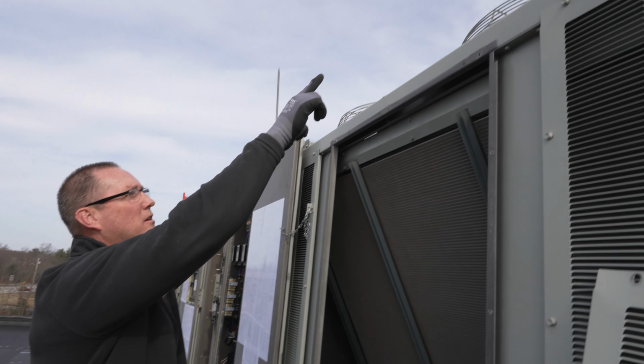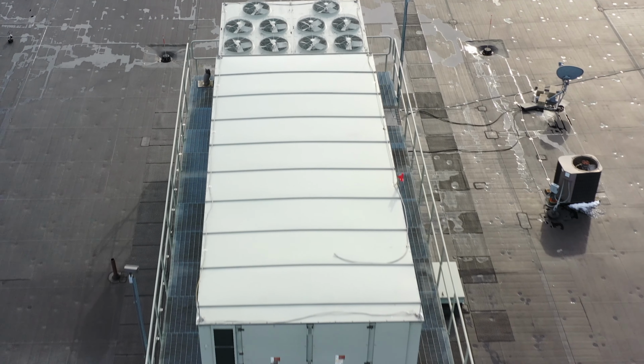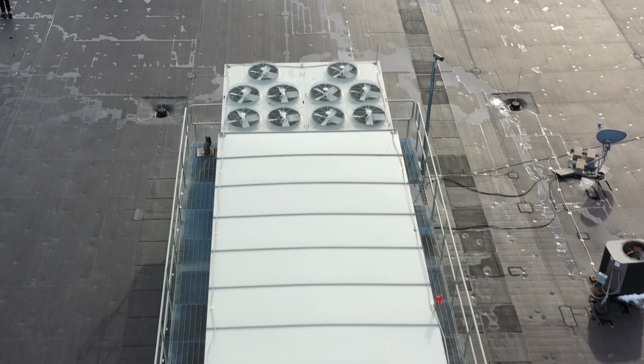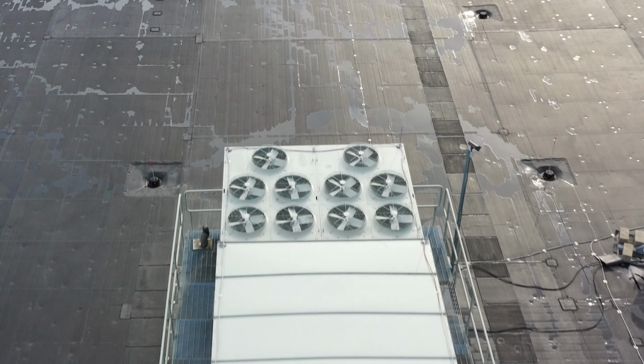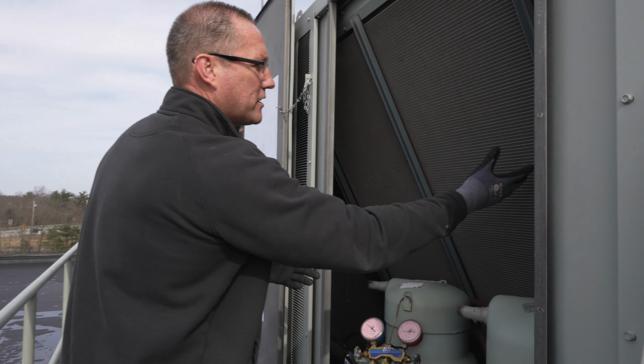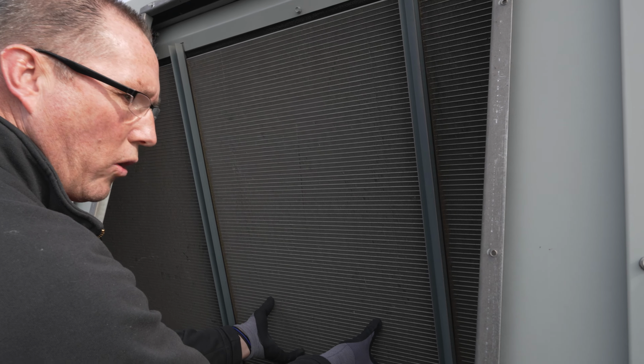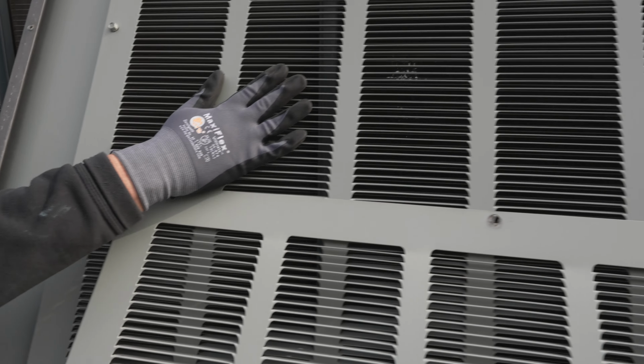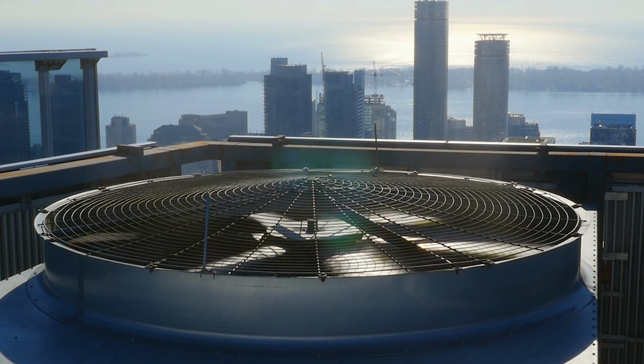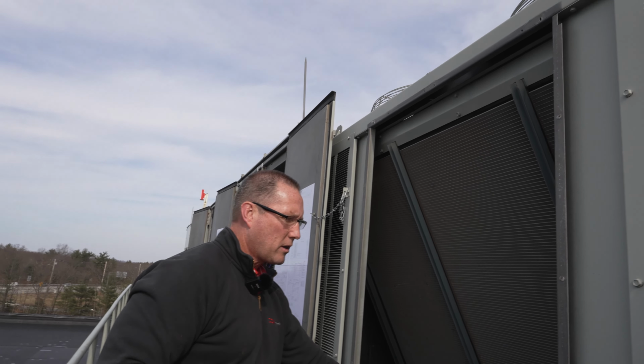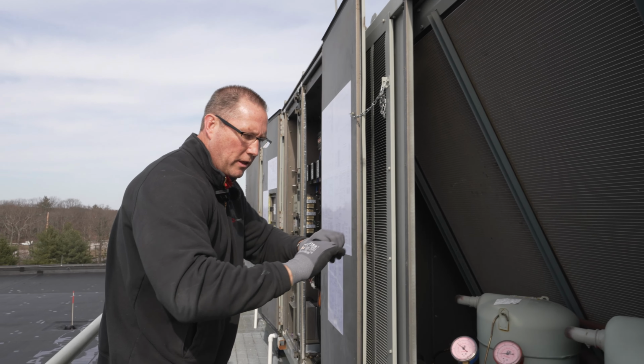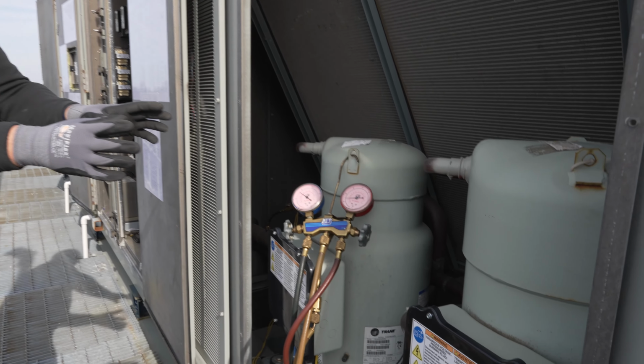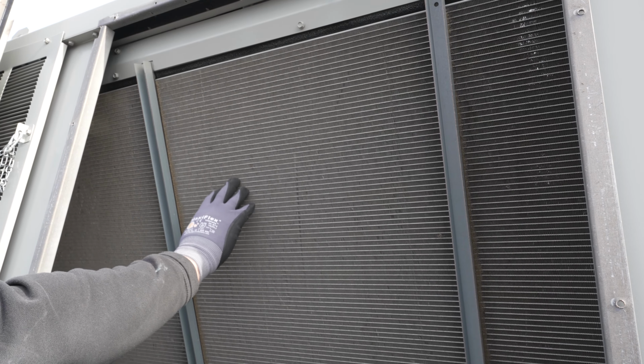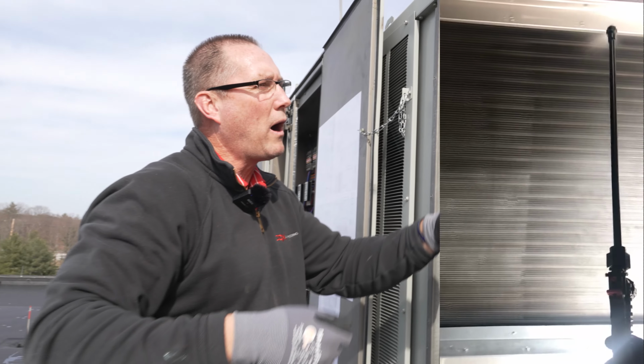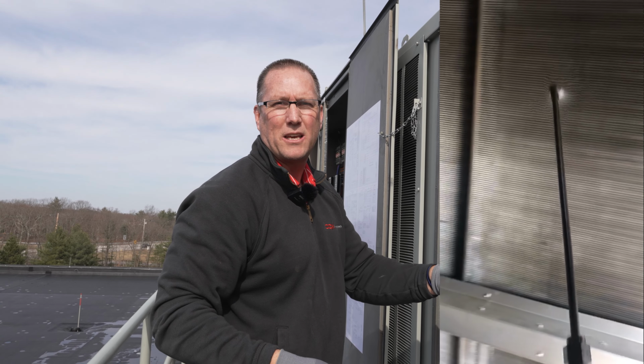On top of this unit here, we have probably 10 fans. We need to make sure that all fans are capable of running in the cooling season. What that does is draw air through these open panels and through the coils, and reject heat that we're pulling back from your building out to the atmosphere. So that's basically what we're checking in this section here. If these coils are coated with pollen or dirt, we're getting the power washers out and we're cleaning these coils.